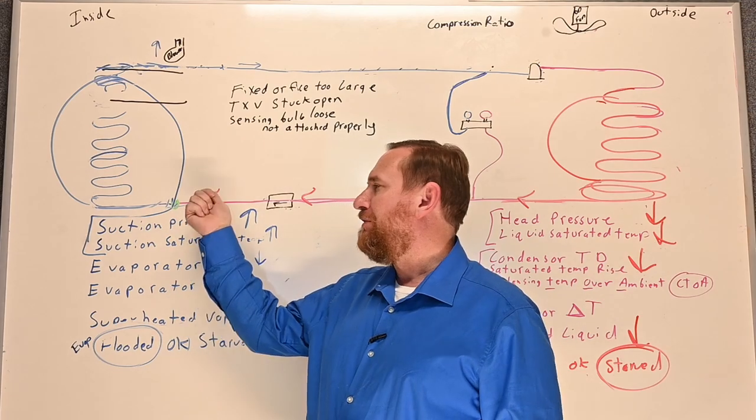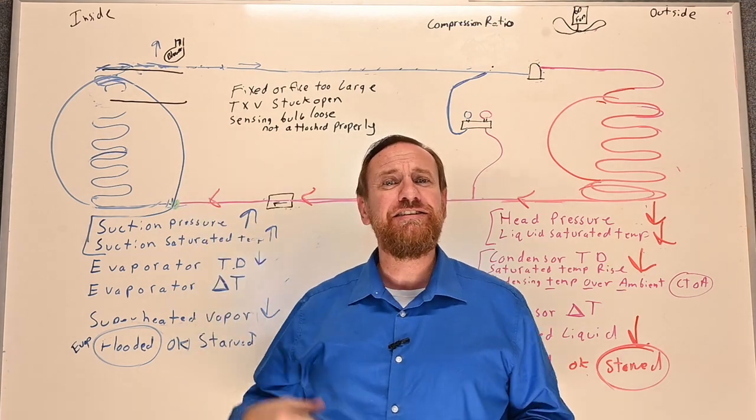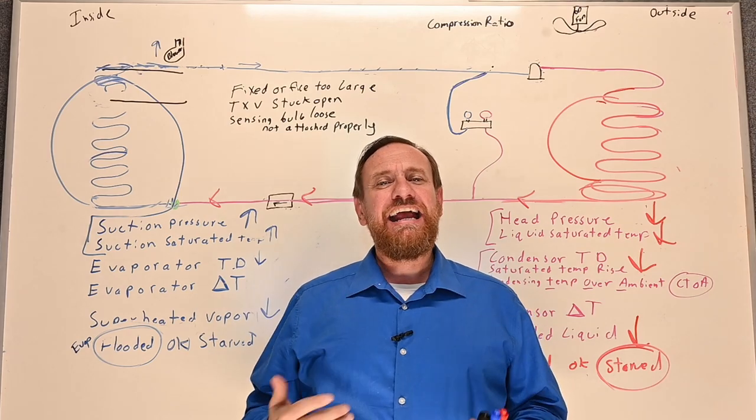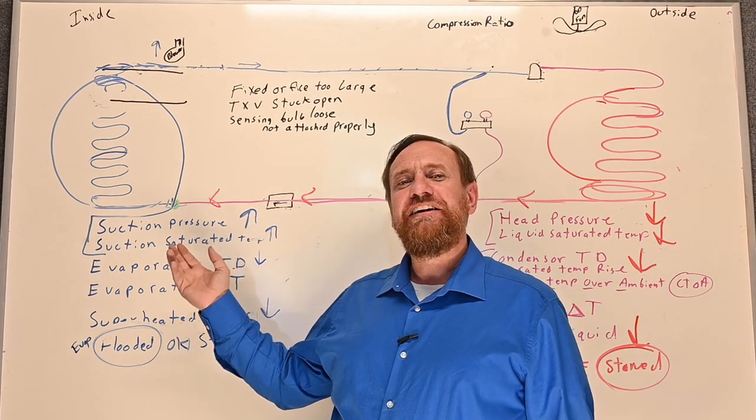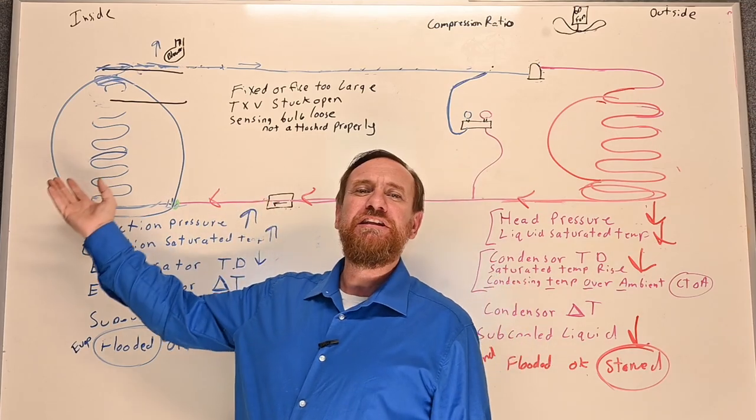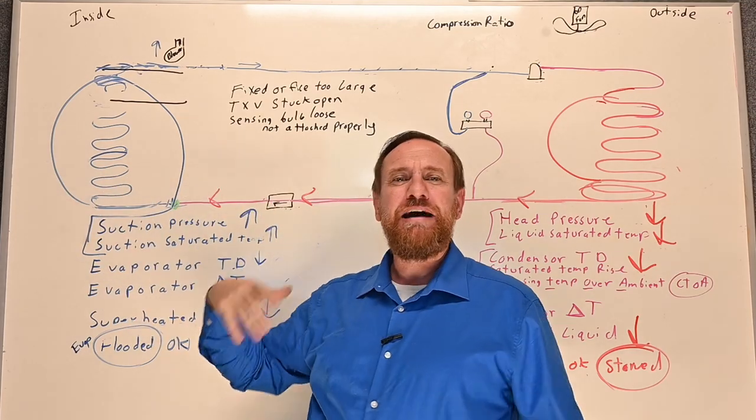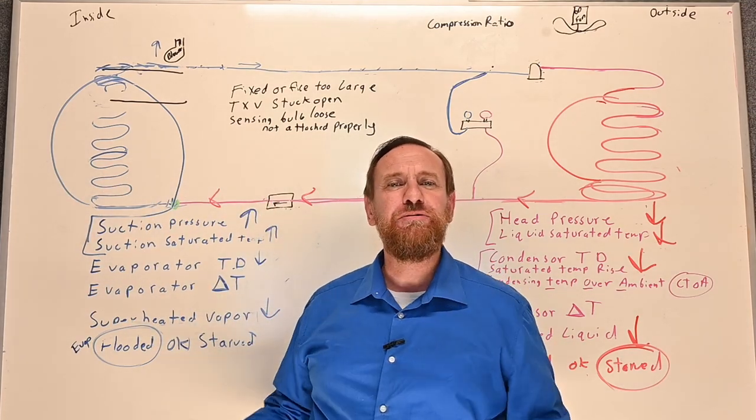I went to another scenario where somebody took the metering device out entirely. They took the metering device entirely out. And I asked the guy, why did you do that? He said, well, the scenario he thought was it would let more liquid in the evaporator. And more liquid means magically more cooling. He didn't say magical, but you get the drift.